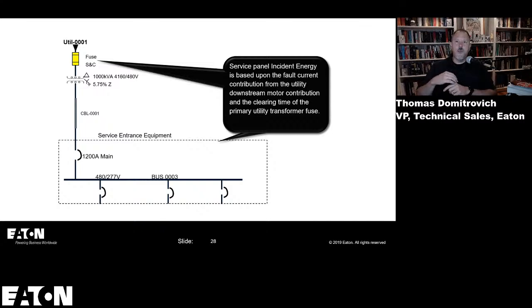What I would like to just walk you through is the value that I see in this solution. This slide is something that I use to help people understand on service entrance, but in reality, the first panel board on the secondary of every transformer has the worst incident energy because of this basic principle that I'm showing you here.